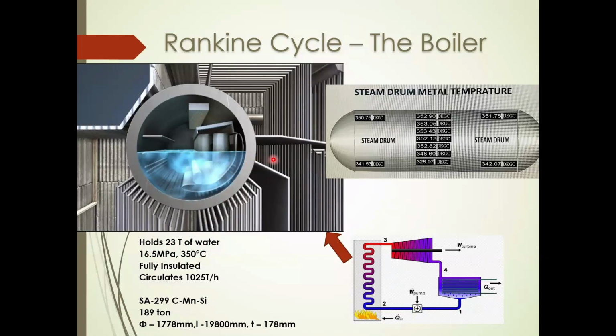Now, according to the manufacturer, if you want to fill the empty boiler, the empty steam drum, the temperature difference between the steam drum and the feeding water has to be less than 50 degrees. So that means if the steam drum metal temperature is 350 degrees, the feeding water temperature has to be at least 300 degrees. This is to avoid damage to the steam drum by uneven expansion.